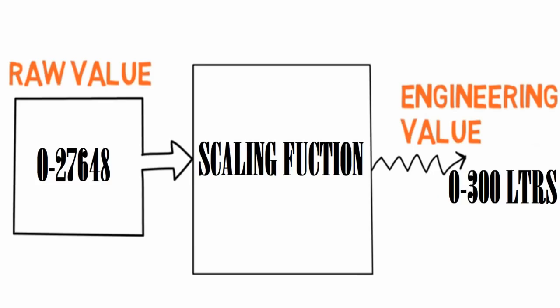To get the actual level between 0 to 300, we have to perform the scaling concept. Scaling means taking a raw value in the range 0 to 27648, passing it through a scaling function, and getting the engineering value. This will be explained in the next session for Siemens PLC S7-300. The process of taking a raw value as input and converting it into an engineering value is called scaling.